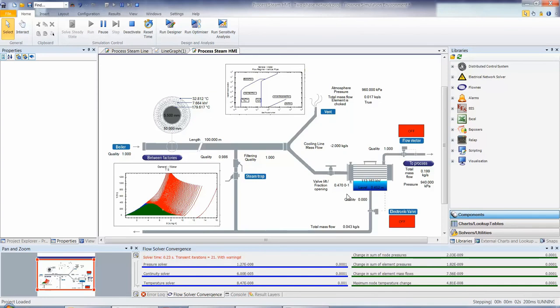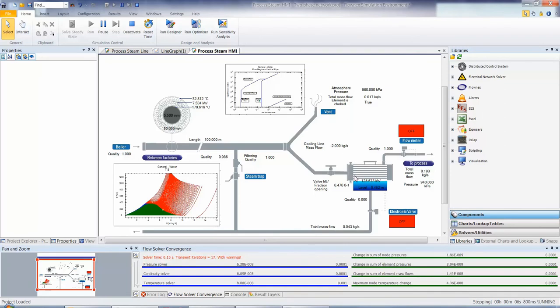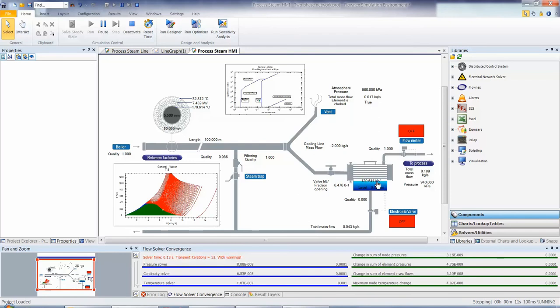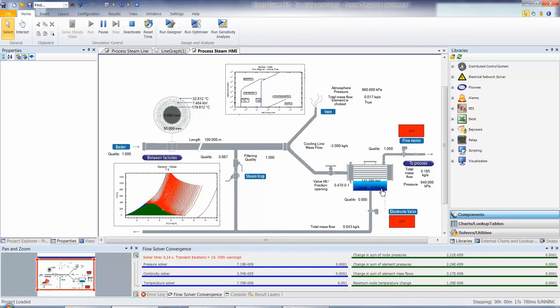Okay, first of all you can see we've now run a script to change the cooling line mass flow. It was around 1 kg per second, we've just increased that to around 2. We can straight away see, because of the increase in cooling flow through our condenser, we have an increase in the heat transfer, and we can have an effect on the level of our system as well. You can see then, there's more condensation because of the increased heat transfer, and the level within our condenser is going to increase.